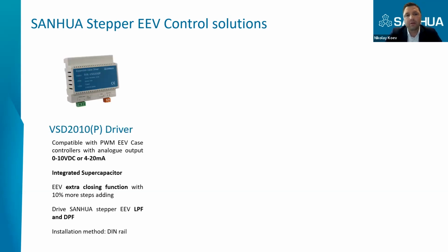We developed a driver which is compatible with PWM, electronic expansion, EEV case controllers. It can receive a 0 to 10 volt signal and converts this signal to a certain number of steps on the electronic expansion valve. So there is no need to change the architecture of the system or the control system. To control the stepper motor valve, you just need such a simple driver.